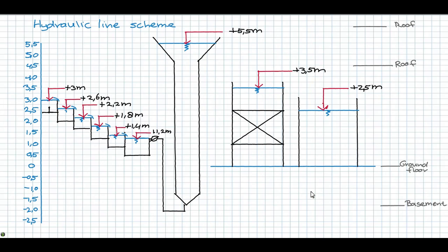When pumping steps are avoided, we have to construct a high building, which is not always possible. Because the softening reactors are relatively high, we normally have a pumping step after the aeration step. Sometimes the reactors are placed below ground level to minimize energy losses, but this is of course a more expensive option.